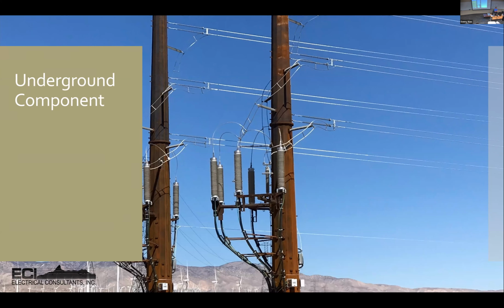Underground transmission is somewhat complicated. It seems like it'd be straightforward, just bury some cable in the ground. The issue is we need to protect that cable. There are grounding concerns, and a lot of other electrical items go into the design, but in general it is as it sounds—you're going to transition from a bare overhead conductor into an underground insulated cable.